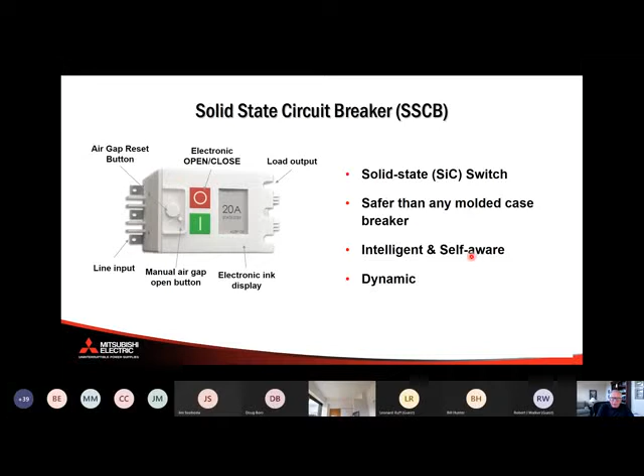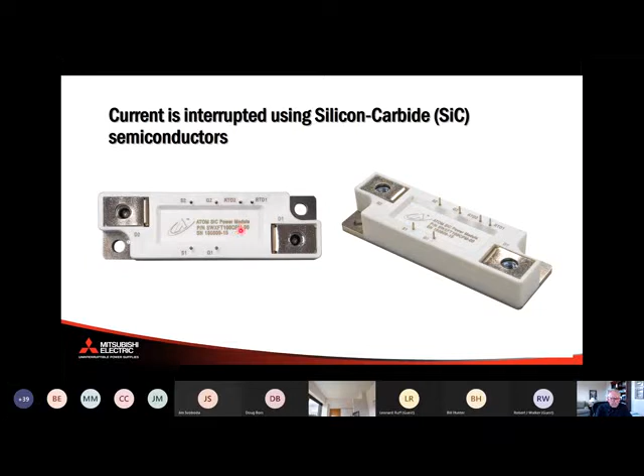Each one of the poles of a single pole or a three-pole circuit breaker actually has a diode inside that you can turn on and off the electricity with. So you're not going to have contacts in there, because when contacts are closed and conducting electricity, and you open them up, you create an arc, and it's hard to open them up, and the arc can be harmful. We're not going to be using contacts. It's a switch, and it's loaded not with silicon, but with silicon carbide because of its wide bandgap.